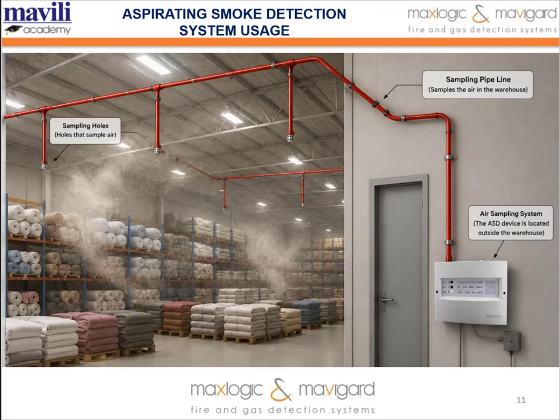Let's talk about the benefits of using the aspirating smoke detection systems in very dusty environments, as you can see. Choosing a fire detection system in very dusty environments is critical, so as to reduce the risk of false alarms, as you know. So aspirating smoke detection systems continuously draw the ambient air through the piping system into the device, and it analyzes it. Dust and dirt filters are the auxiliary equipment of the aspirating smoke detectors. It prevents particles in the sampled air from directly reaching the detection cell and contributes to more stable system operation. So this reduces the risk of dust-related contamination, also false alarms, and protects device life and device performance. So you can use this as a point in your area.